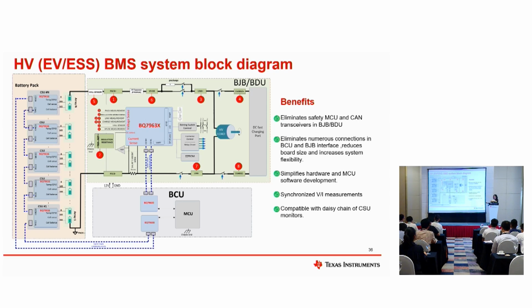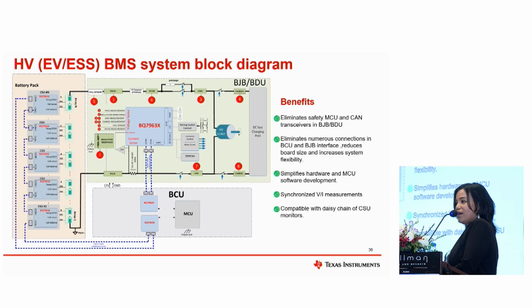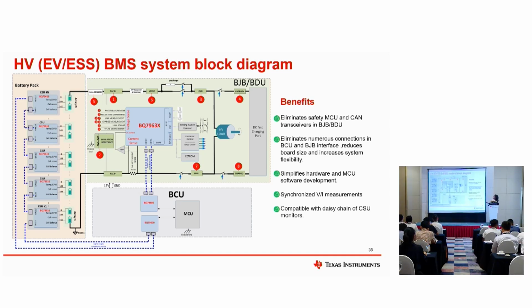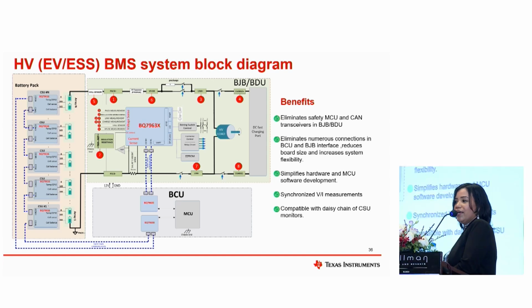One important thing is for current sensing on high voltage applications, we sense on the low side because it's a low voltage solution. That will also include your coulomb counter and your current shunt, and this gives all of the results, which can be synchronized together with the TI daisy chain. So you can get all that information back all the way from your high voltage signal to your MCU and do your SOC, SOH calculation for the high voltage system in a pretty accurate manner.